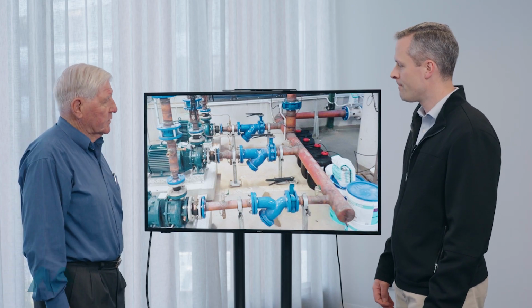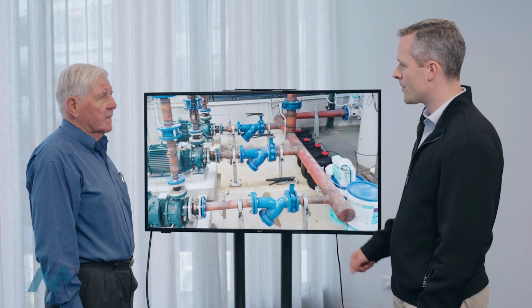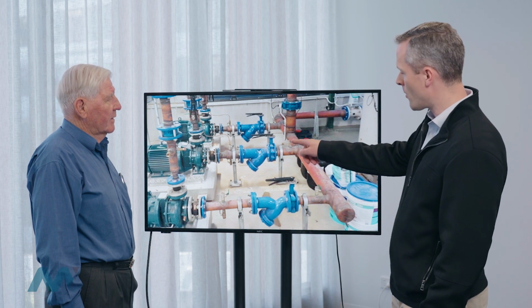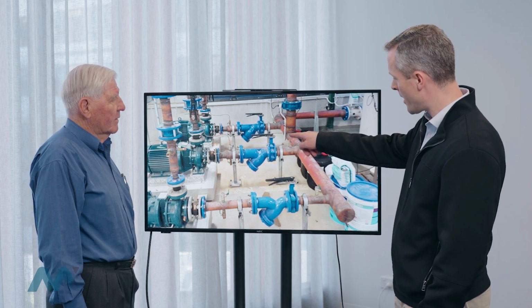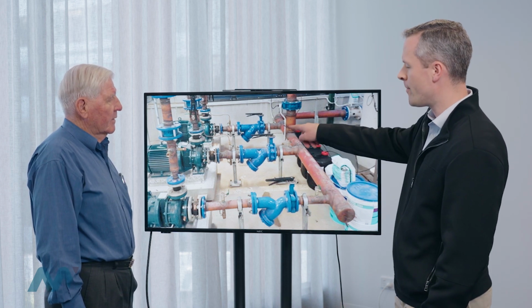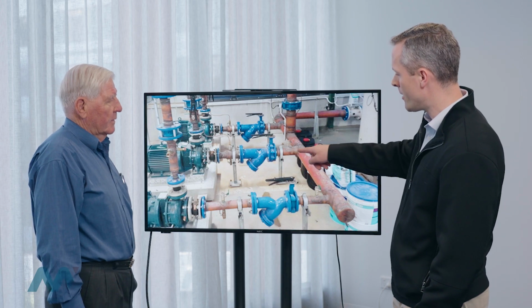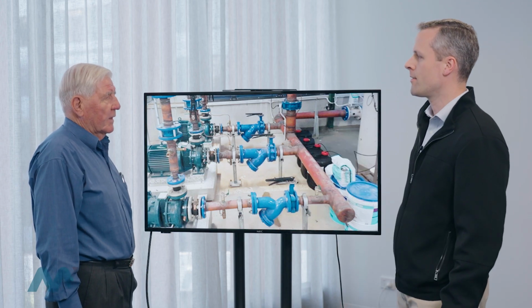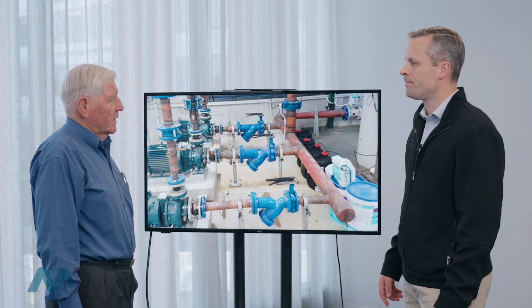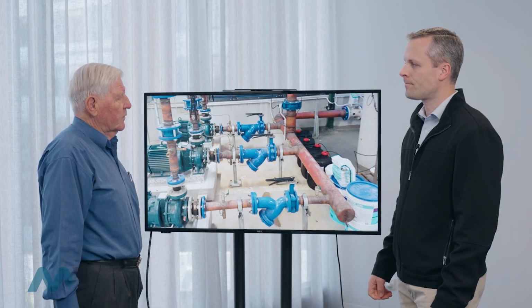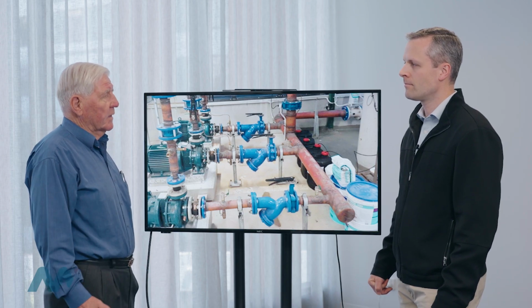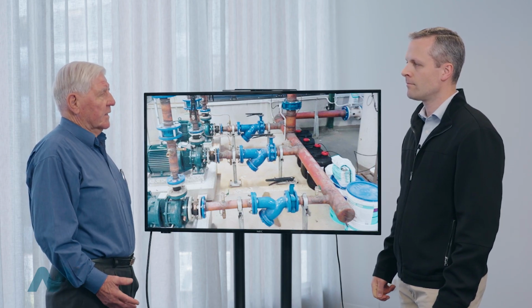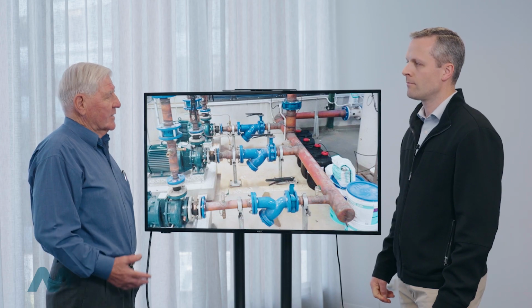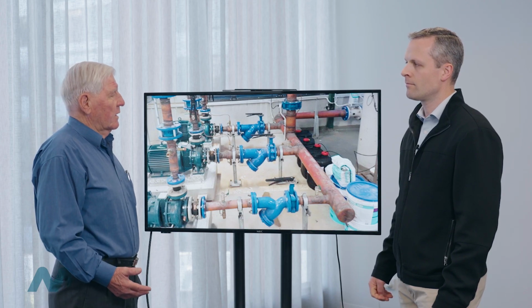Which piece of pipe are we talking? Because they're different diameters. Certainly. So we had 2.9 metres per second in this 125 millimetre header, meaning that it was higher going down the branches. So normally speaking, we're looking for velocities into the eye of the impeller of around 1 metre a second. Okay, that's good for a suction design.